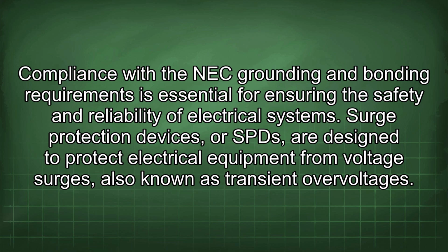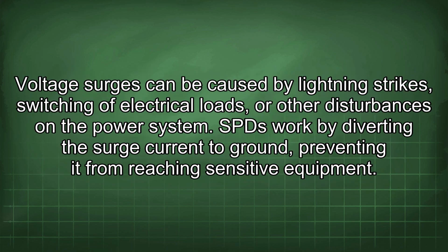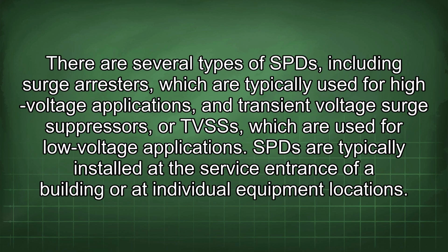Surge protection devices, or SPDs, are designed to protect electrical equipment from voltage surges, also known as transient overvoltages. Voltage surges can be caused by lightning strikes, switching of electrical loads, or other disturbances on the power system. SPDs work by diverting the surge current to ground, preventing it from reaching sensitive equipment. There are several types of SPD, including surge arresters, which are typically used for high voltage applications, and transient voltage surge suppressors, or TVSSs, which are used for low voltage applications.